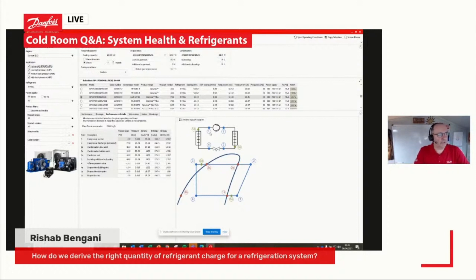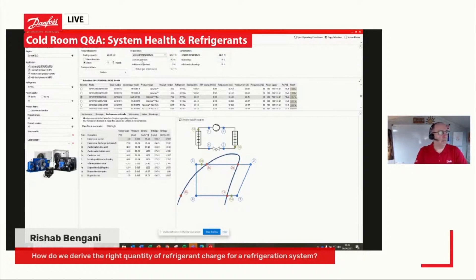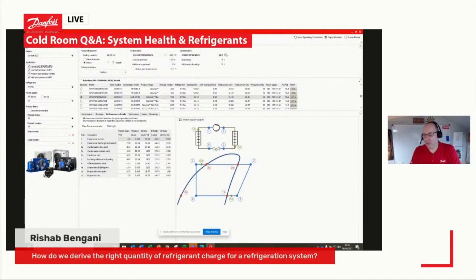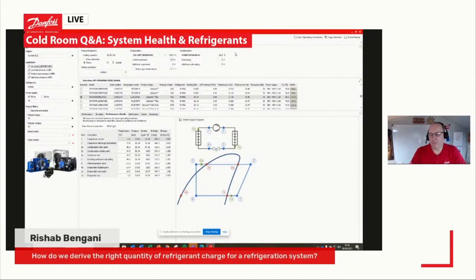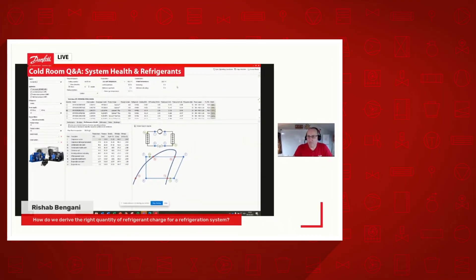We've got compressor suction as point 1, compressor discharge as point 2, and it will tell you your temperature and pressure that you would expect on that system given the evaporating temperature and the ambient temperature. So this is a very good way to double-check on-site when you're commissioning a system — to make sure that your suction pressure, discharge temperature, liquid temperature, and so on are there or thereabouts where they should be. It's something I use quite a bit on-site with condensing units just to double-check.